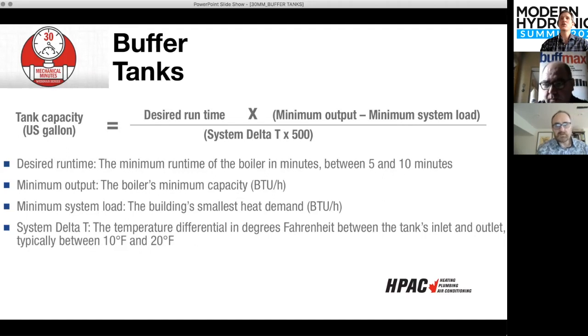Okay, and you talked about sizing buffer tanks. Steve, maybe you could help us with that. Yeah, so one of the main purposes of a buffer tank is to reduce the short cycling that can be an issue in a boiler. So when you size it, it's variable.